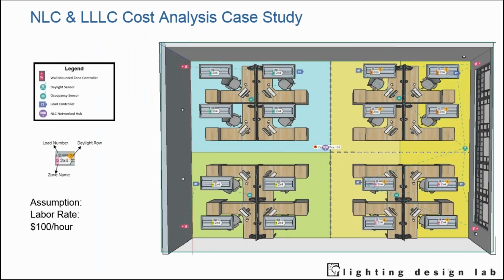I wanted to have this space on the right-hand side. It's an open office that has 4 workstations, and we have 2 systems that do the same things. The first one you're seeing here is your network lighting control zone grouping application, where these purple devices are your load controllers, these circles are occupancy sensors, this one over here is a daylight sensor, and these are your normal dimmable 0 to 10 volt fixtures, with wall stations at the side.